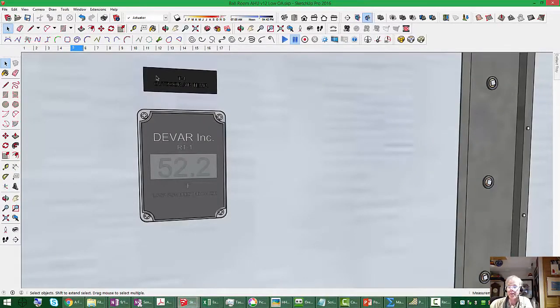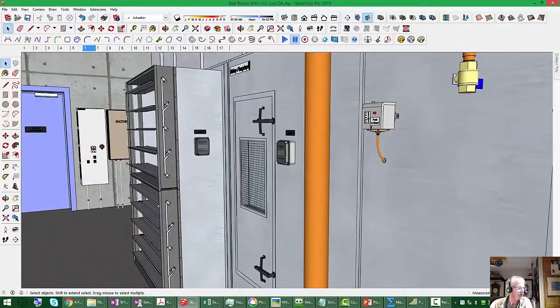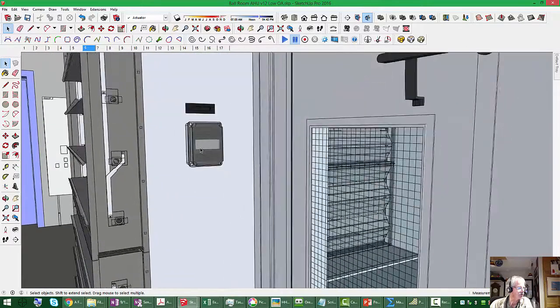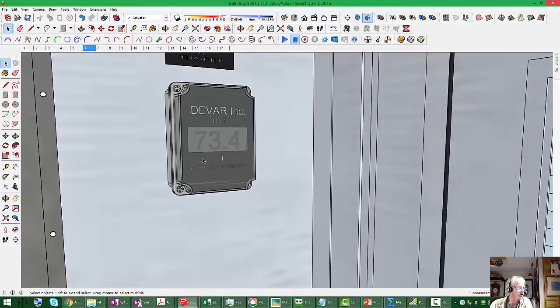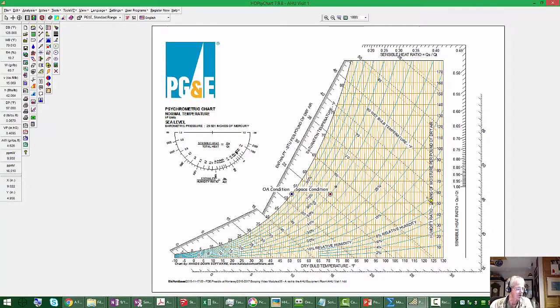If we look at the return section, if our sensor's right, it's about 73 degrees in the return air, 73.4 to be specific. And so let's add that point on our psych chart, okay? So the air starts at the space and it flows through a duct to the return of the unit, and it picks up a degree or so of heat.